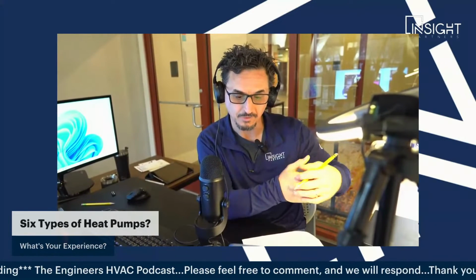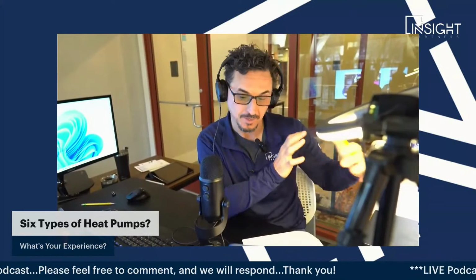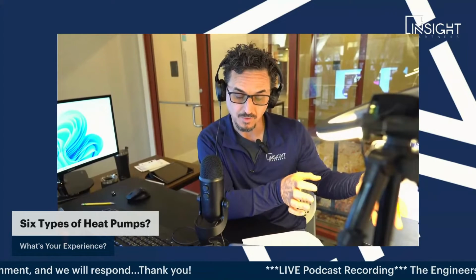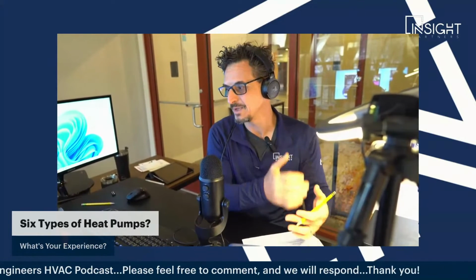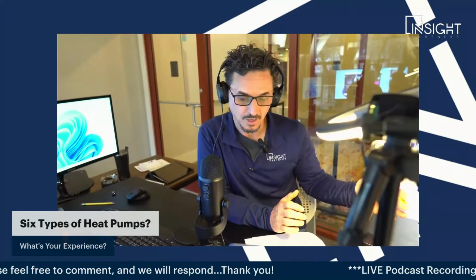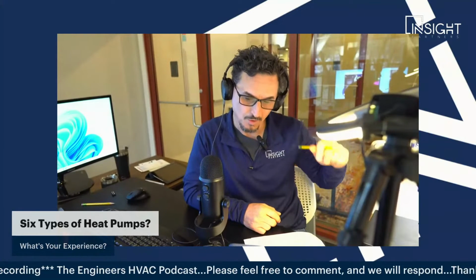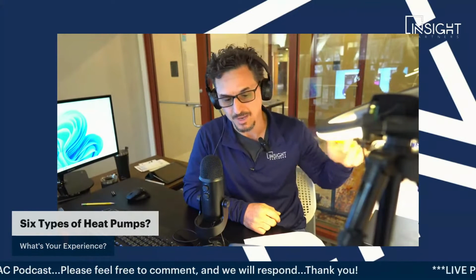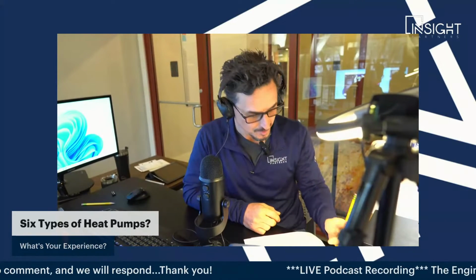So heat pump chillers, heat pump water heaters—these products are made to be installed indoors. You may have a basement area which you can cool with the heat pump water heater, extracting the BTUs from that area, and then use that heat to heat your water so you can eliminate your boilers. Typically those go along with a bank of hot water storage tanks. You could do that pretty easily, especially in a domestic situation, because the hot water use profile on domestic applications peaks hard in the morning for a couple hours, then hard in the evening, then doesn't use much hot water the rest of the day.